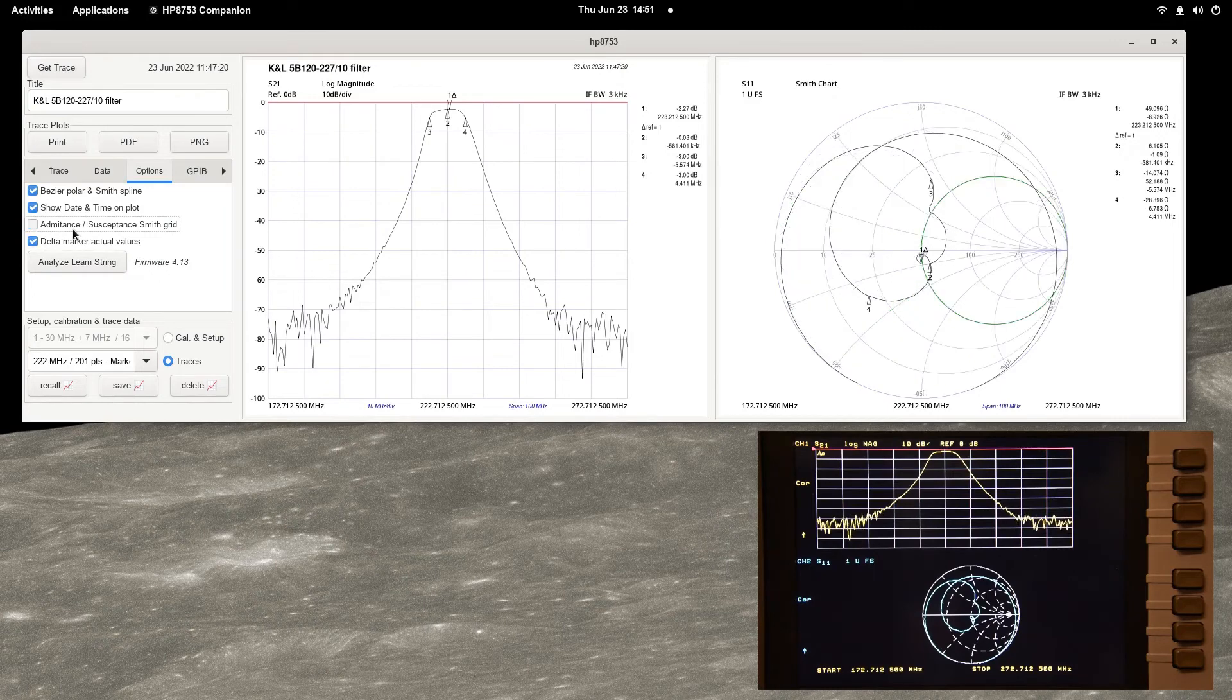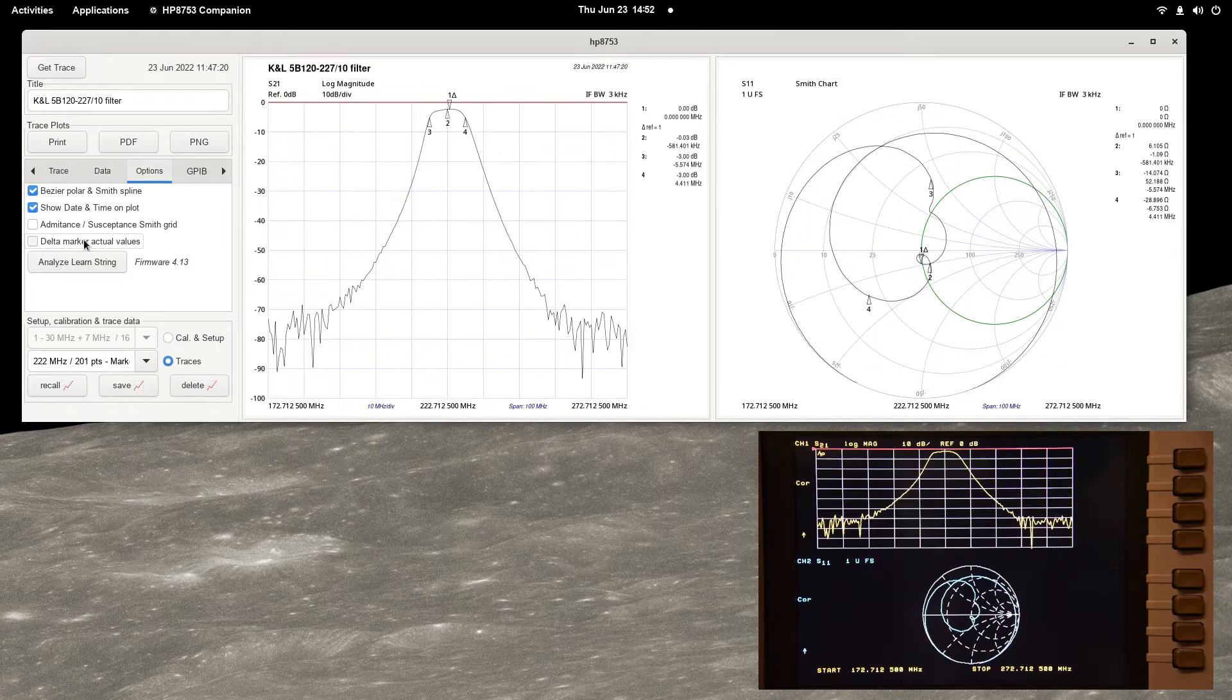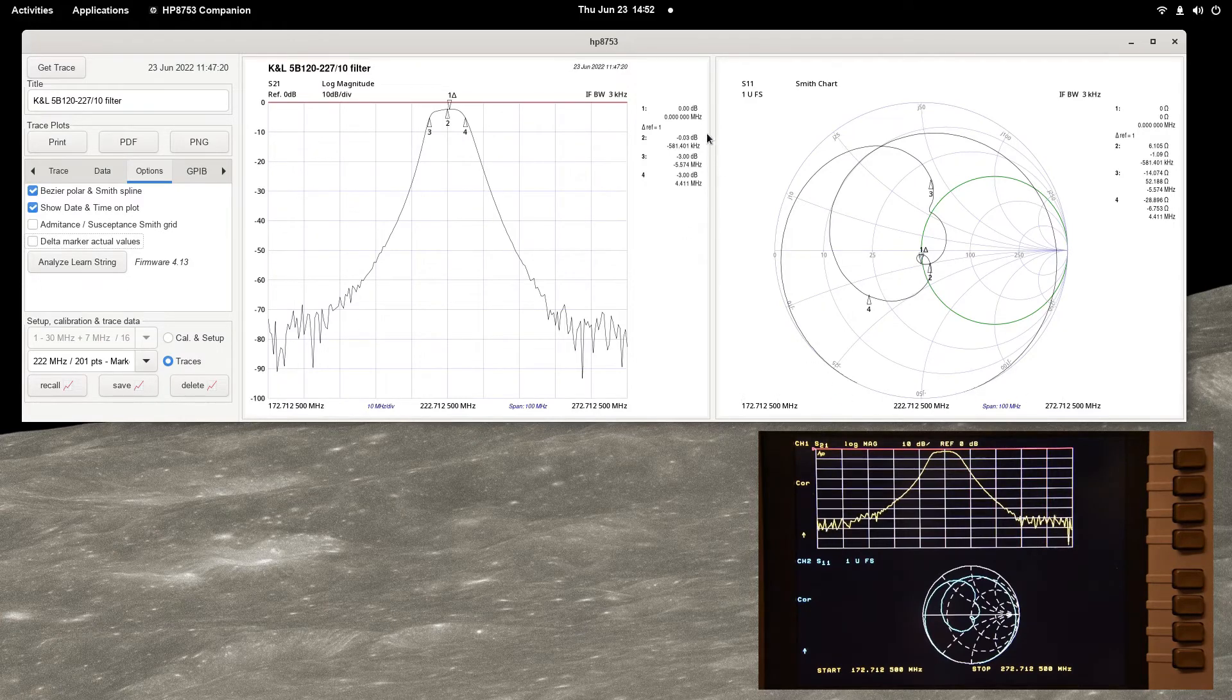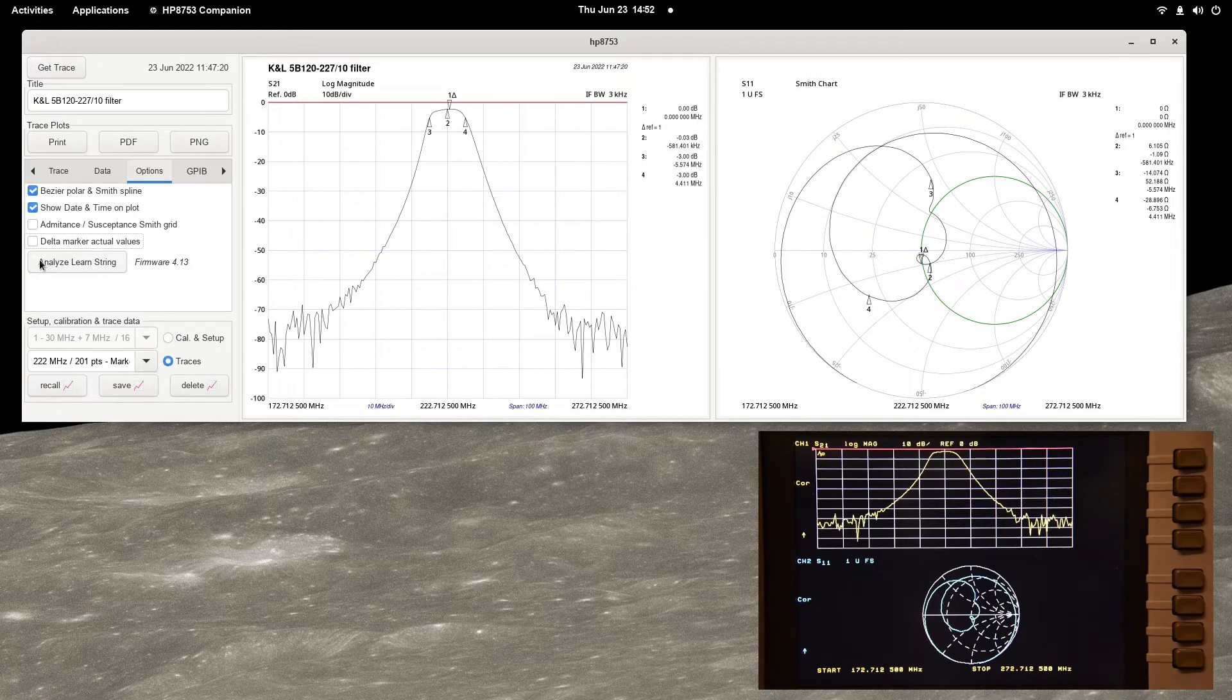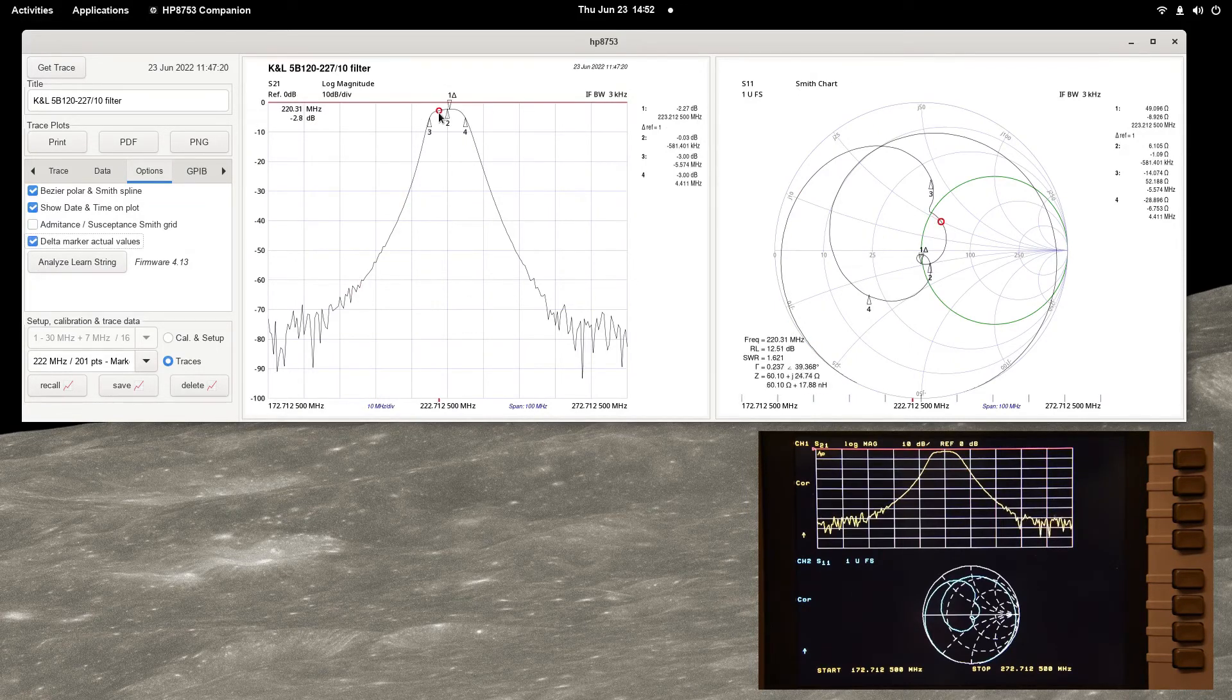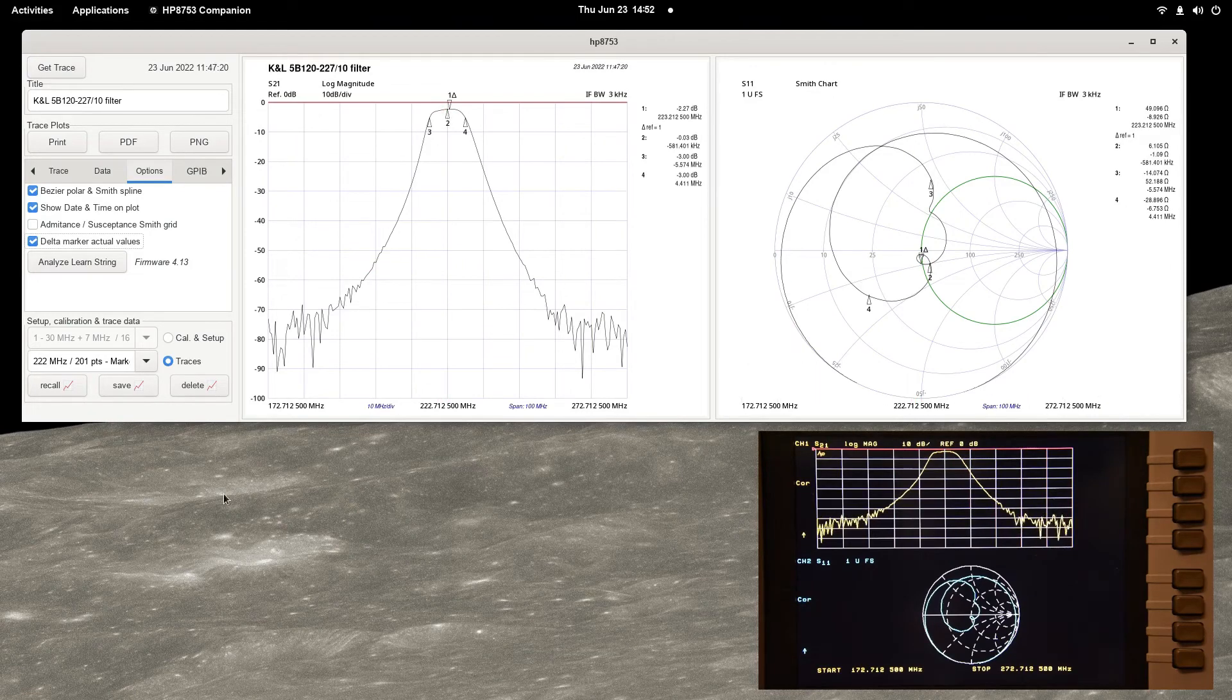The last option displays the actual stimulus and response values for the reference marker when delta markers are enabled. The HP 8753 sets these to zero on its display by default. The behavior is mimicked when this option is not checked.